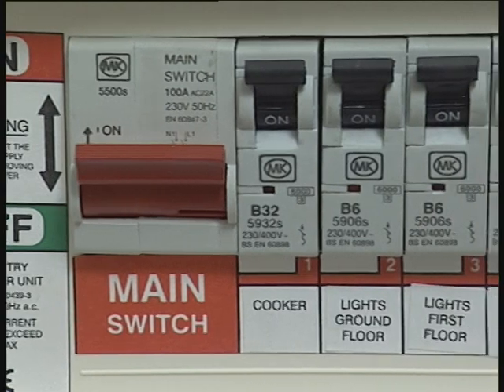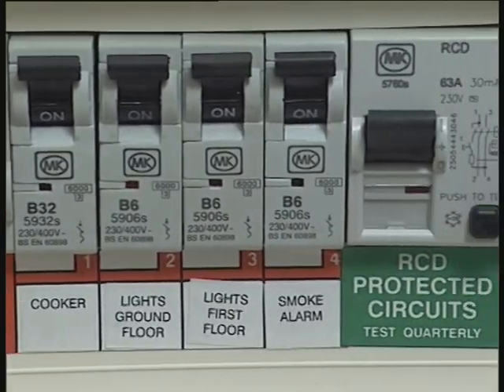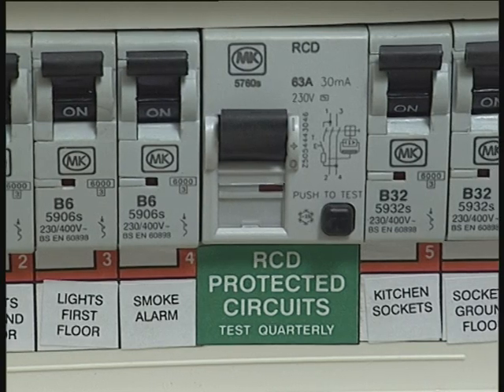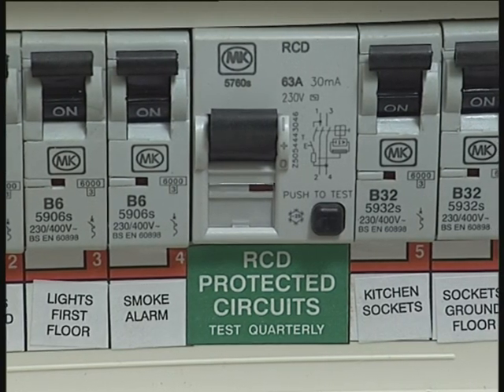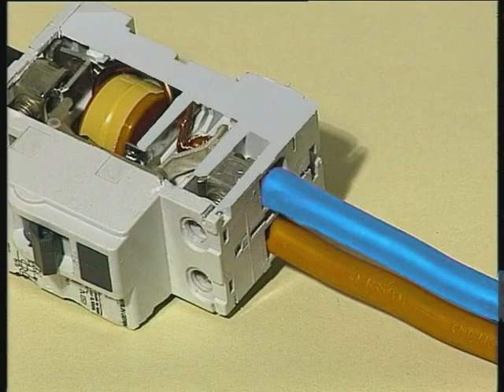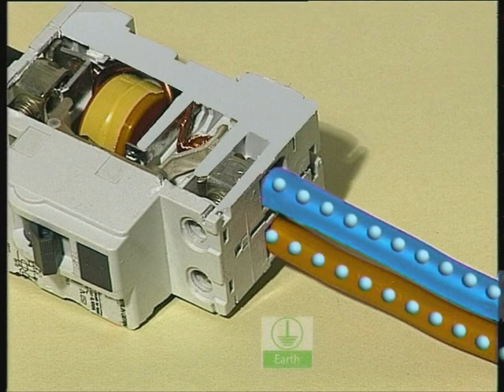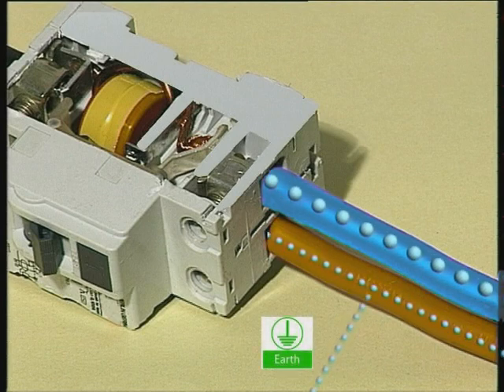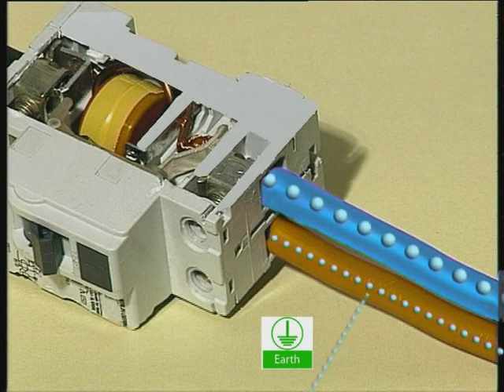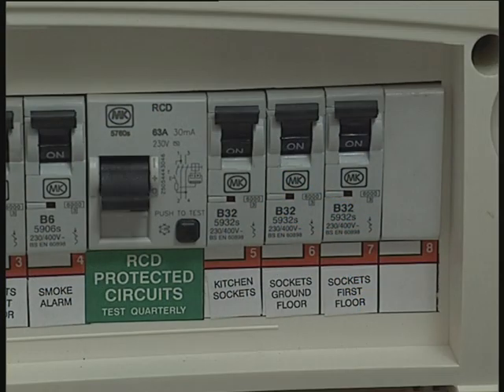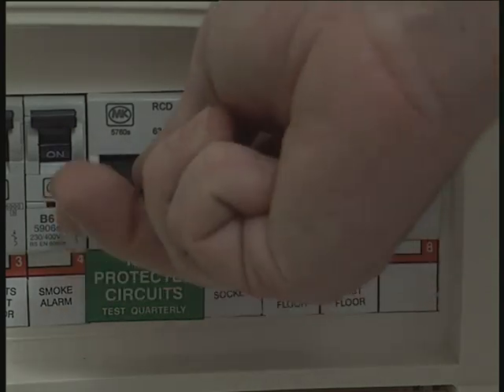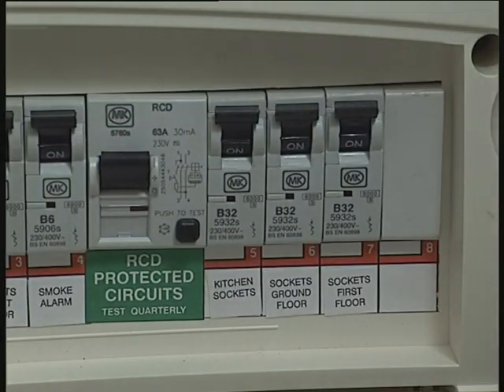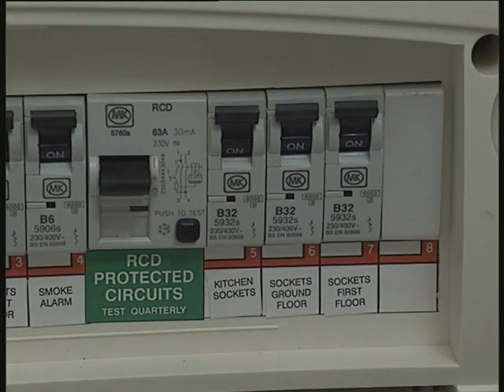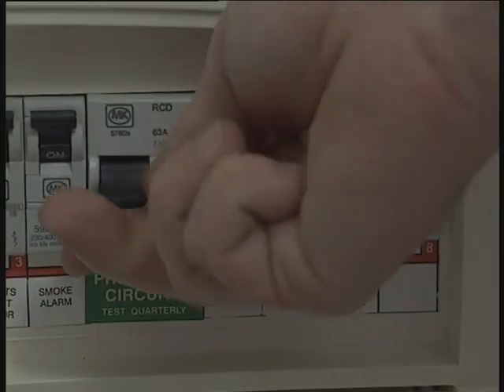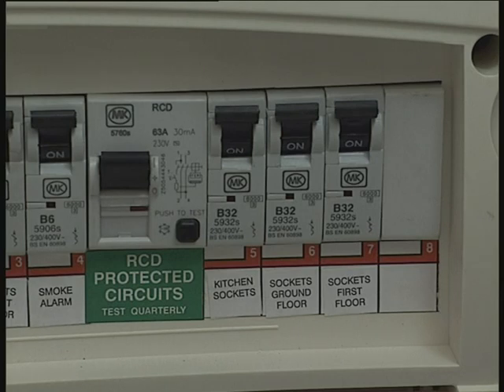The only way to automatically disconnect the electricity when someone touches an exposed electrical conductor is to use a device known as a residual current device, or RCD. This clever little device can detect any imbalance in the electrical supply. So, when some electricity escapes to Earth, perhaps through a person, the RCD will disconnect the electrical supply very quickly. To help ensure correct operation, RCDs should be tested at least every 3 months by means of the built-in test button. Unfortunately, residual current devices are not usually found in installations that are more than 15 years old.